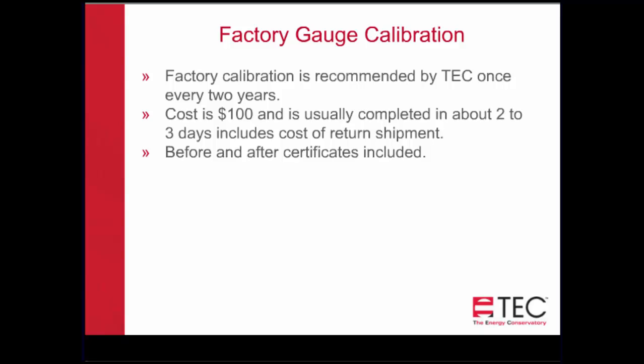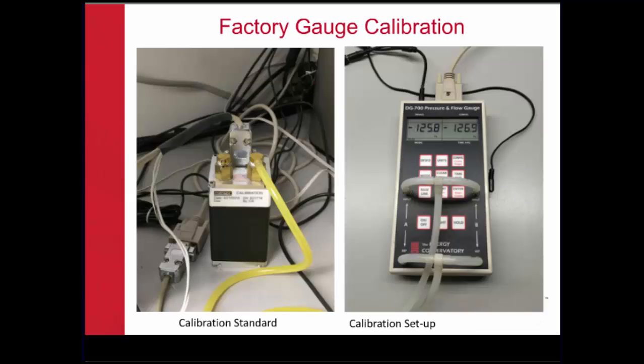So we recommend once every 2 years. The cost is $100 and is usually completed in about 2 or 3 days. And the $100 includes the cost of return shipment. There are both before and after certificates included, meaning we test your instrument as we receive it, then we perform a recalibration on it and provide you with another certificate that gives you all of the information.